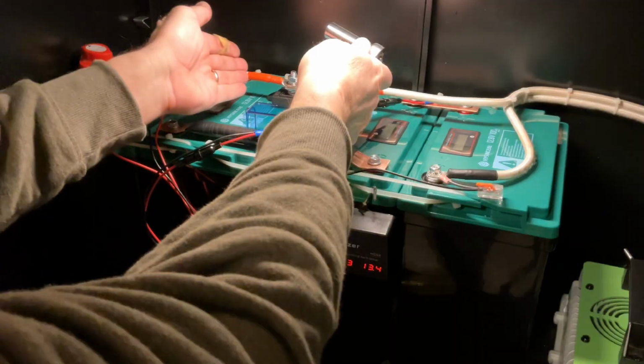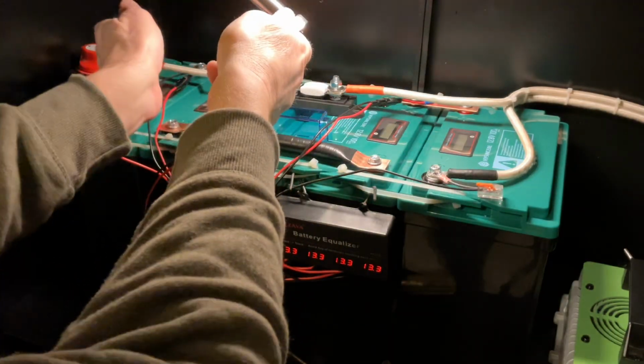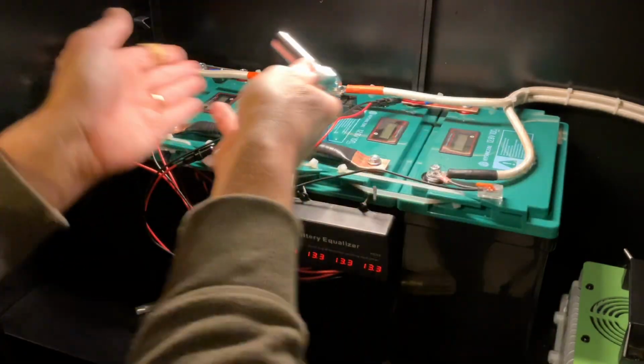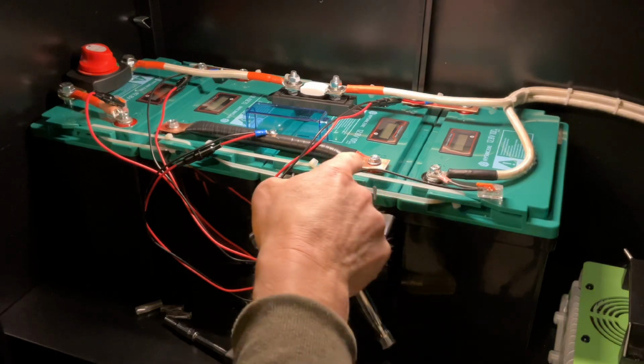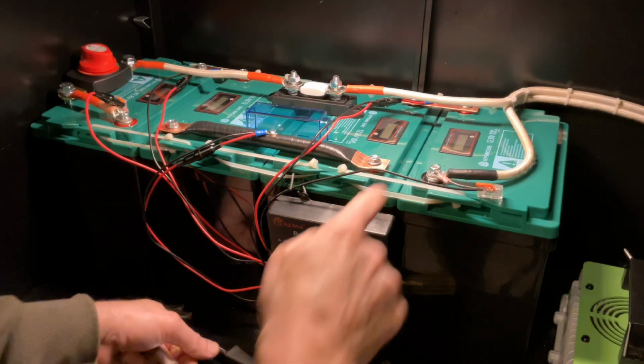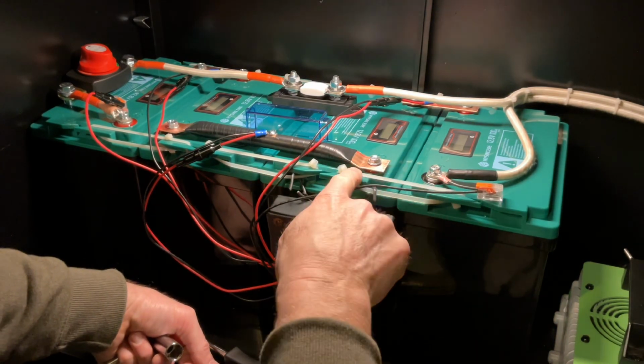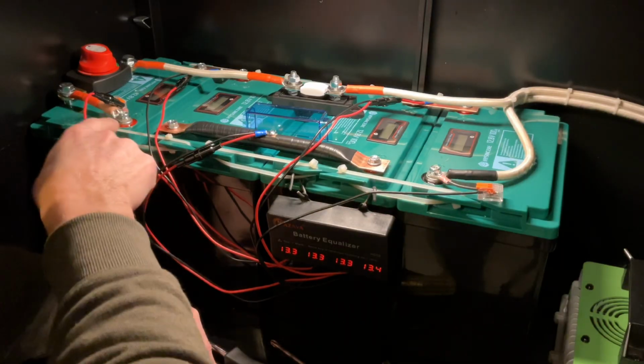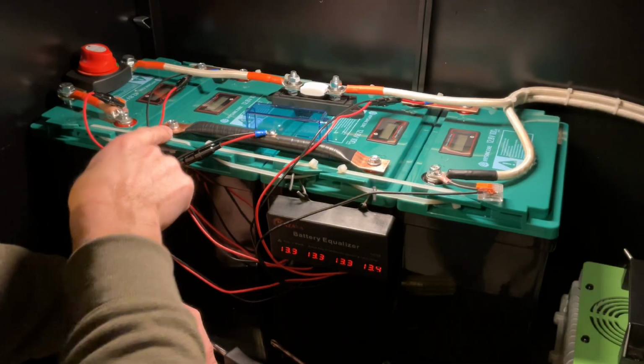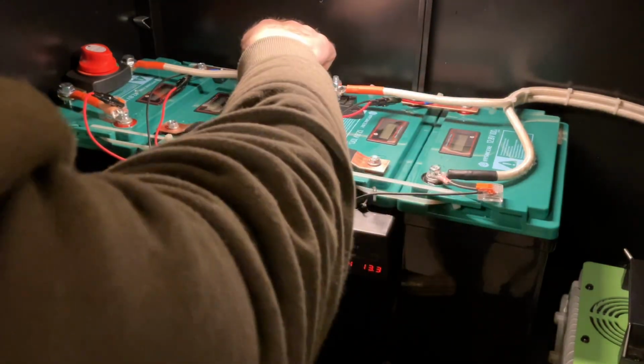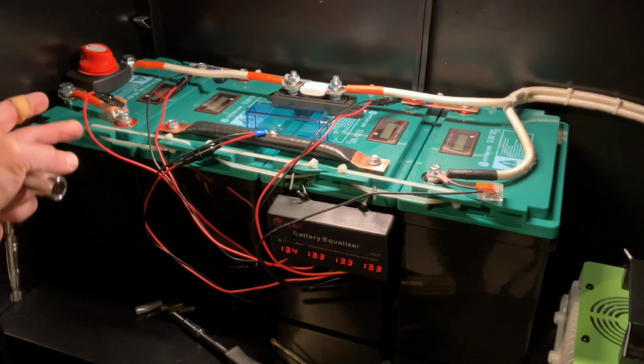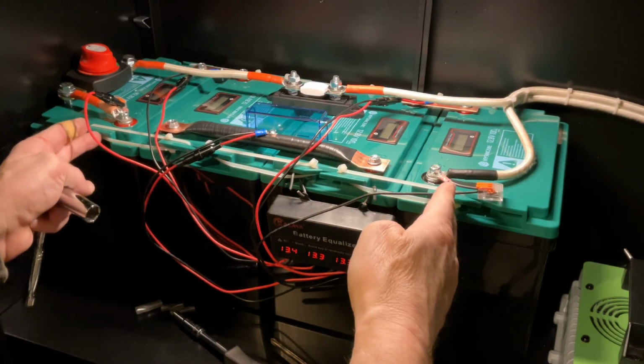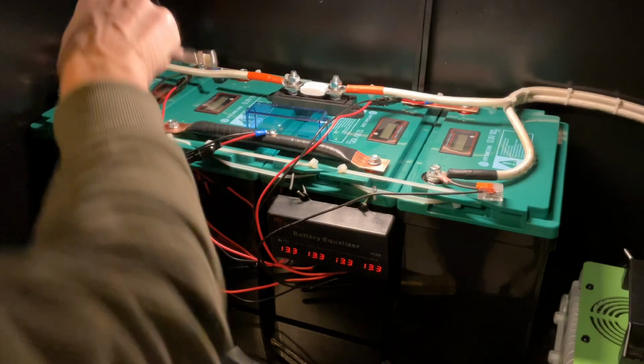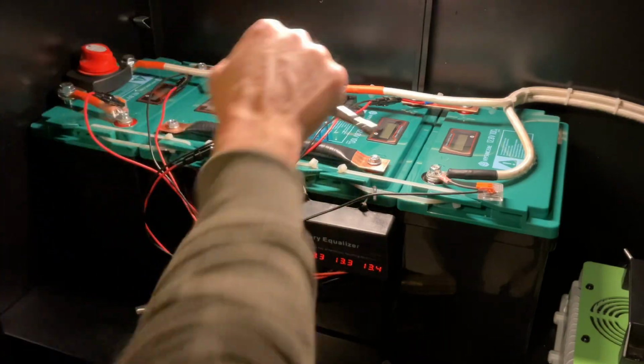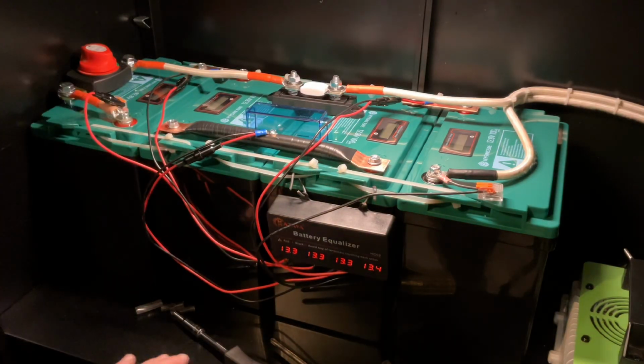You can see I'm nowhere near the main negative and main positive of the pack now, which gives me a little bit more clearance. These are the highest potential junctions you're going to see now. There's 24 volts between these two terminals, 24 volts between these two, and 24 volts between these two. The only location on the battery where you'll see 48 volts is from the two ends. So it's a little bit safer since a tool isn't going to reach that, and you're less likely to put your hand on each end of the battery.